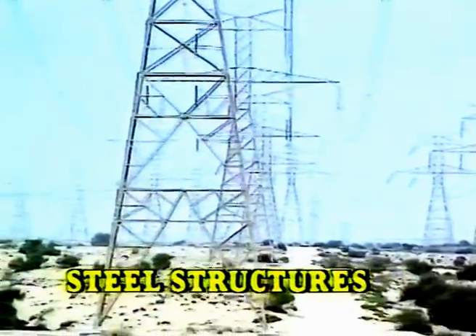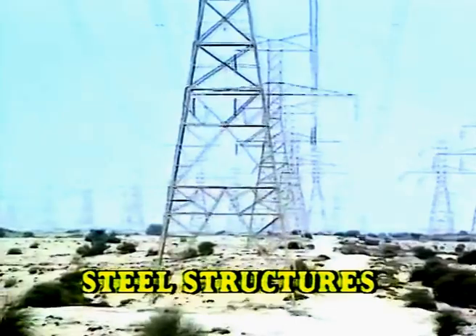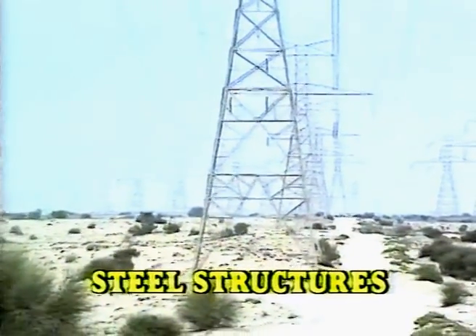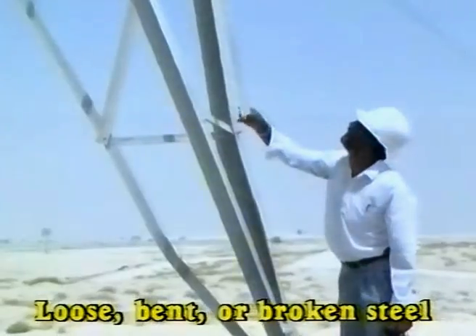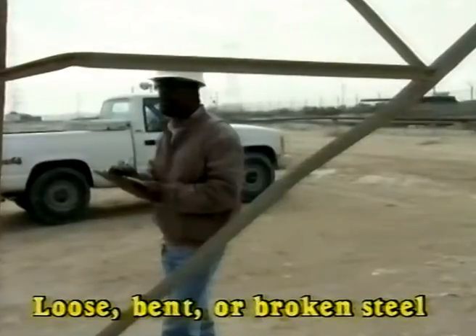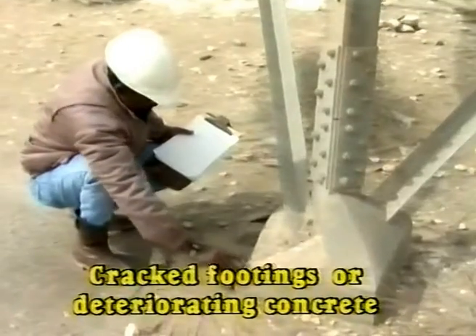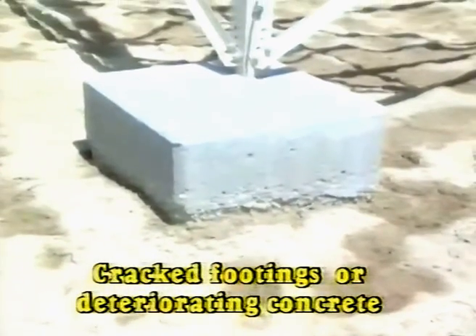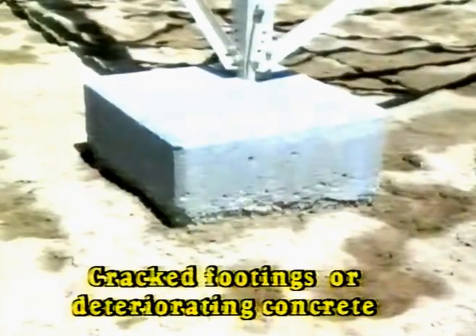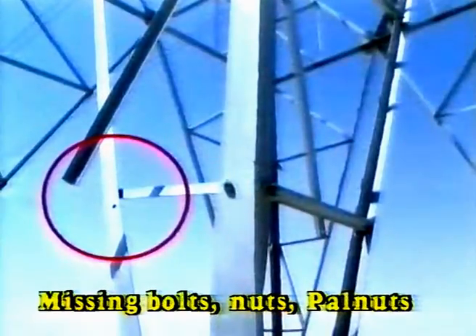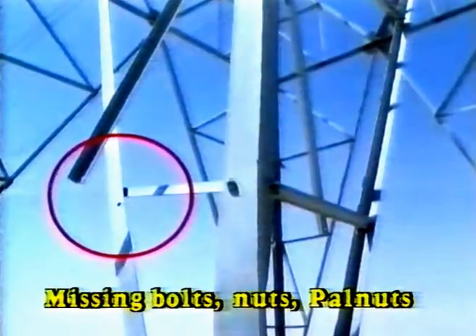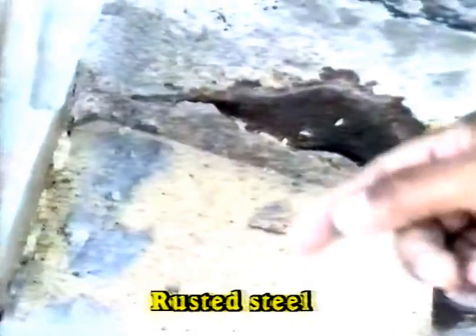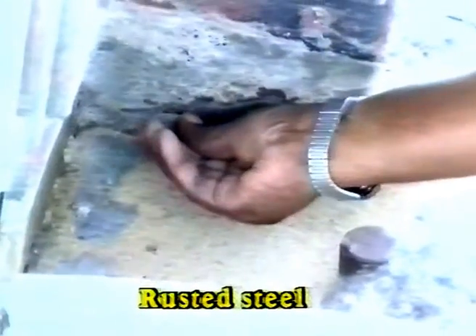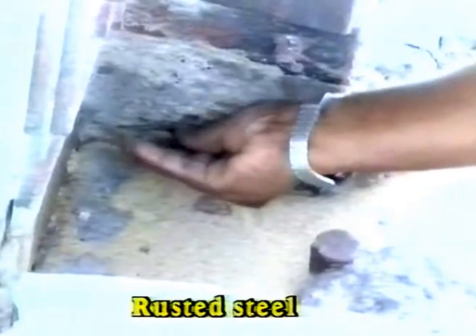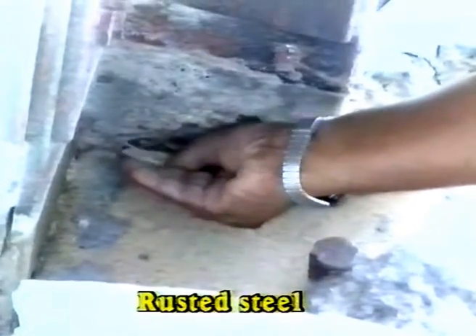Steel transmission towers may vary in height and design. The following are specific items to be checked on steel structures: loose, bent or broken steel, cracked footings, or deteriorating concrete, missing bolts, nuts, pal nuts, rusted steel. Special attention should be paid to steel where it enters the footing concrete.